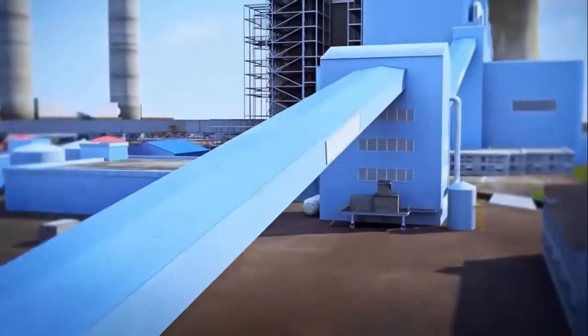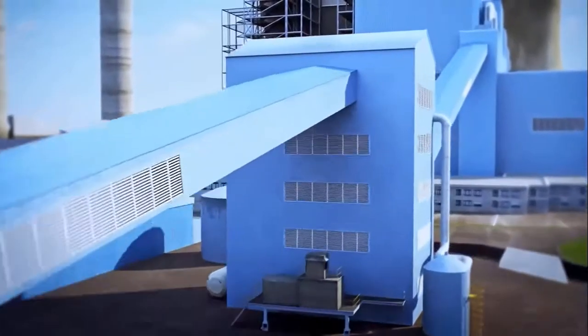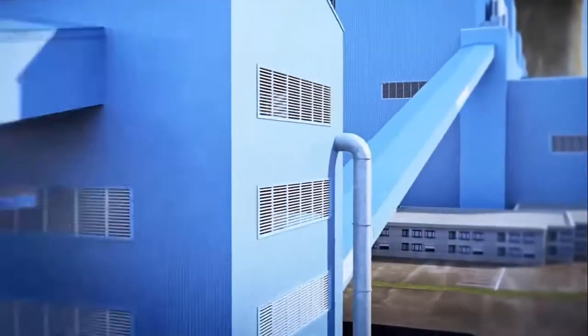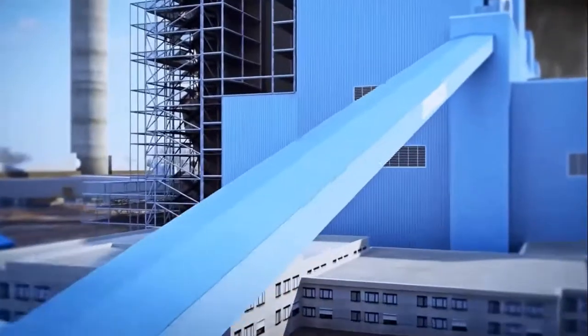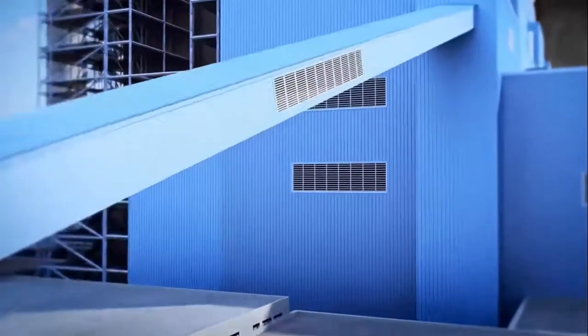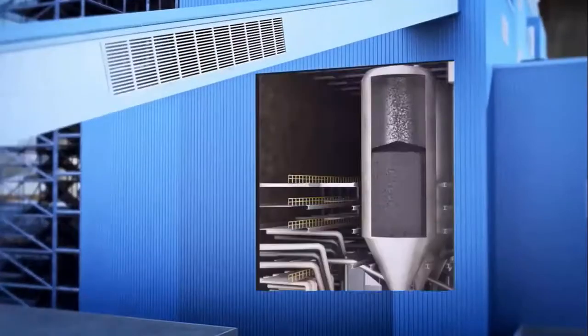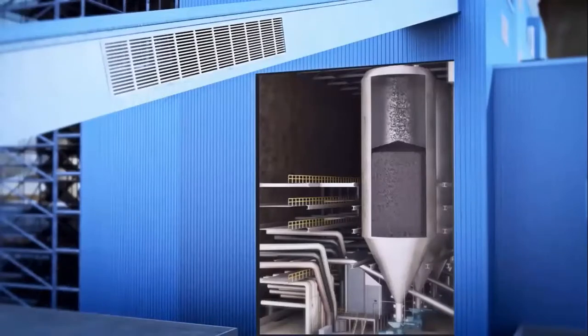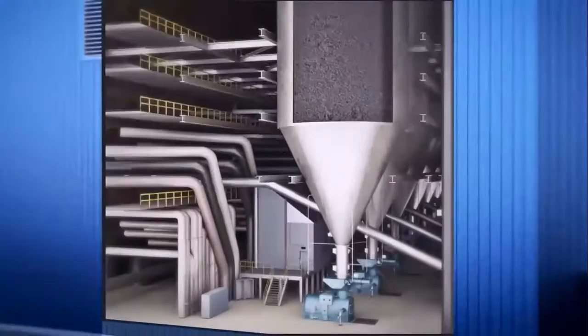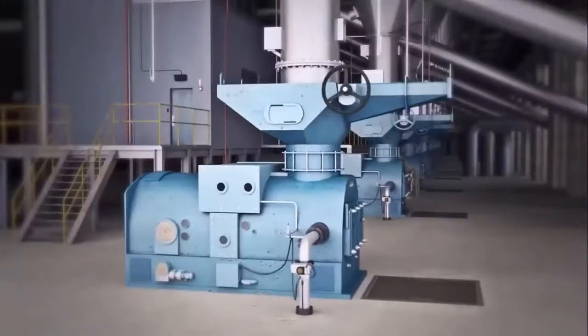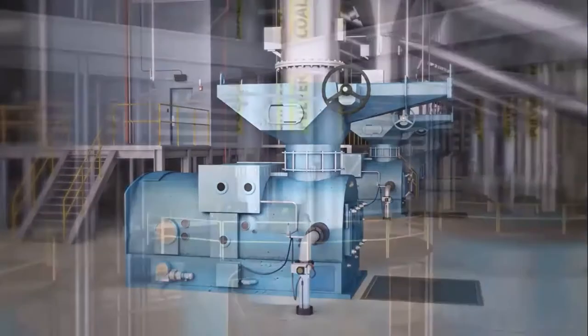Coal moves into the plant on a conveyor and is stored in a series of silos, each one leading to a feeder, pulverizer, and ultimately to the boiler. At Plant Miller, we have four generating units, and each unit has seven silos feeding into one single boiler. The coal within each silo falls into a feeder, which measures and controls the flow of coal into a pulverizer.